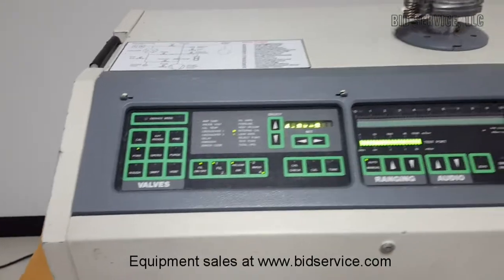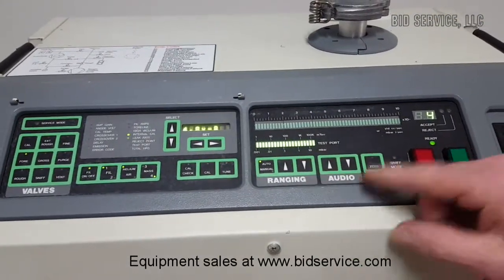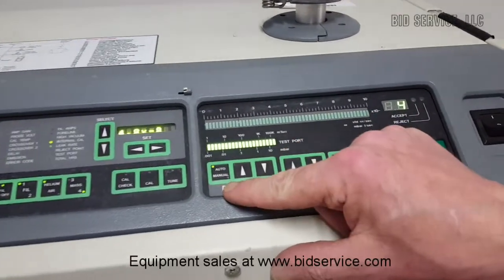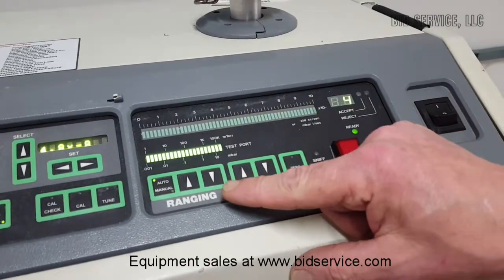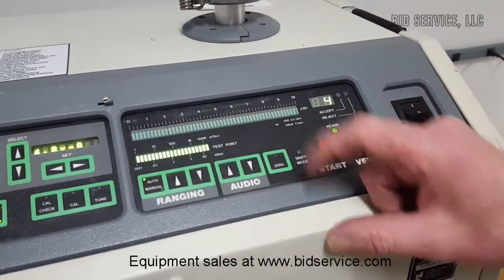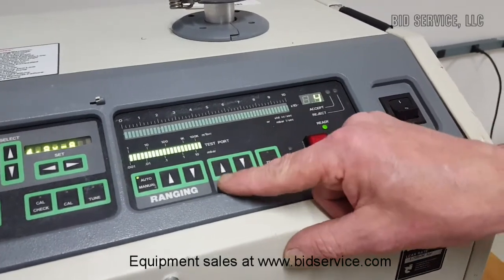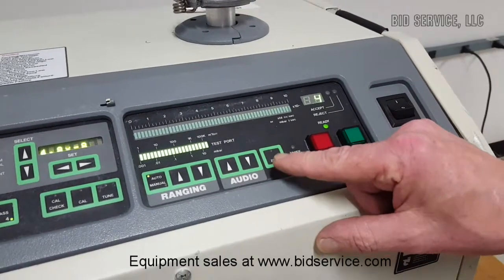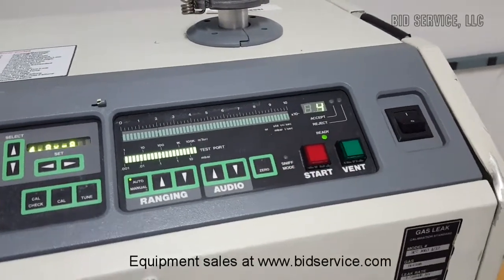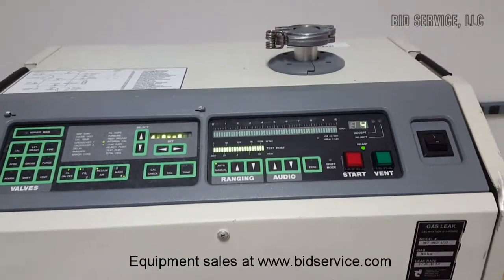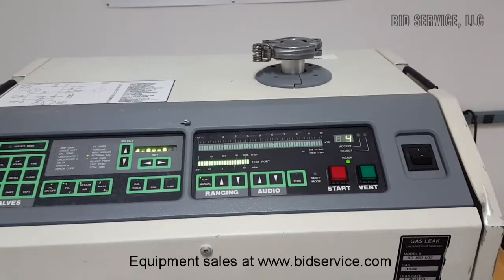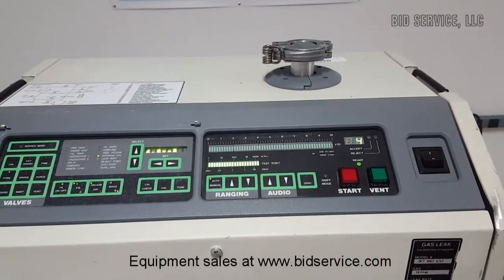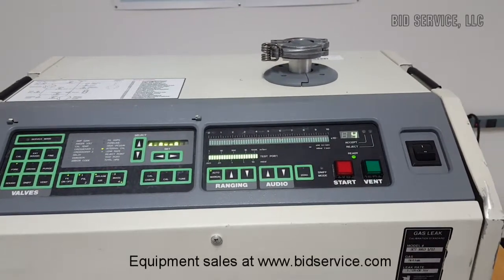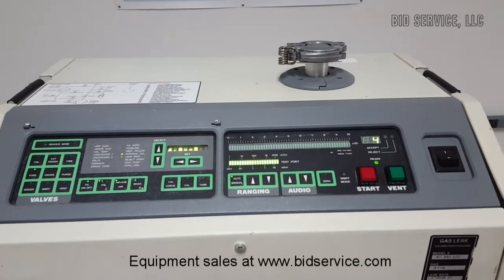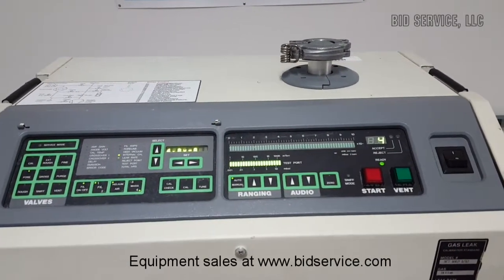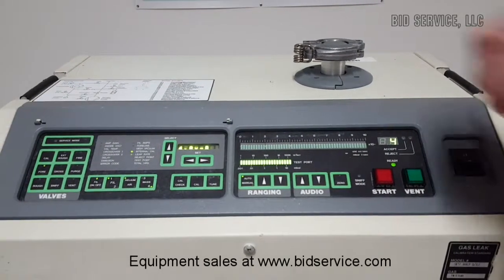The standard mode, which is the operator's side, is very simple to use. There is both manual and automatic ranging that allows you to change the different ranges. There's also a volume control for the audio and a zero. What zero does is, many times when you have different workpieces on and off, you may expose this to air in the room, and even in the air of the room and around the machine there is what they call background helium. This helium can also affect your measurement, and by zeroing out that background helium, it would not be part of your actual measurement. This is your test port here.